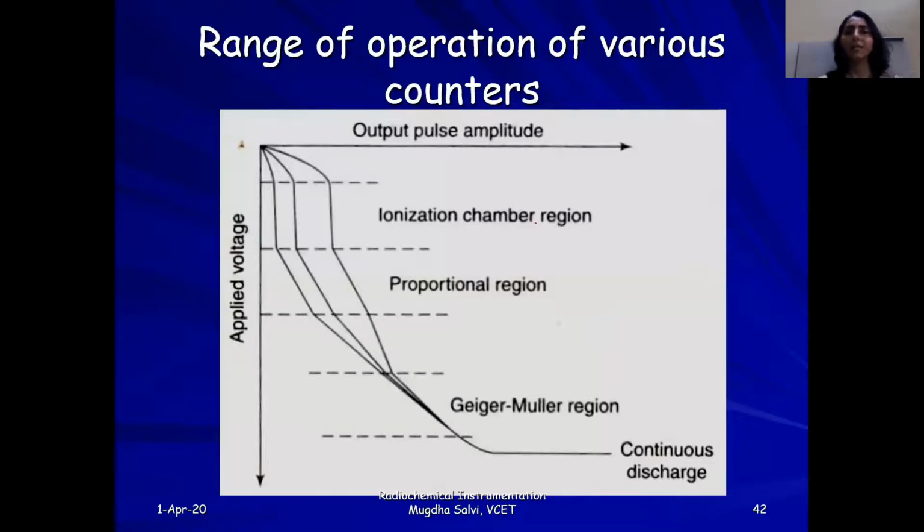Now, all these radiation detectors fall under the category of ionization chambers only. That means we have a gas which is present. There is an anode, there is a cathode, and current flows through it. The gas inside will get ionized because of the radiations that are entering, and these will eventually create electrons, which we will measure as current. They will differ only in the operating voltage.